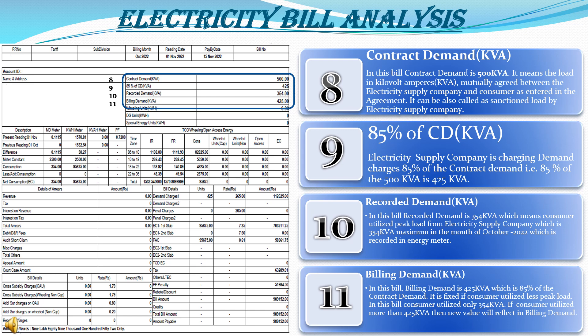The consumer has to utilize up to 500 KVA. If he uses more than 500 KVA, other charges will be applied. The next term is 85% of contract demand — the electricity supply company charges 85% of the contract demand. For 500 KVA, 85% means 425 KVA. The recorded demand in this bill is 354 KVA, which is the actual peak load the consumer utilized from the electricity supply company, maximum in the month of October 2022, as recorded in the energy meter.